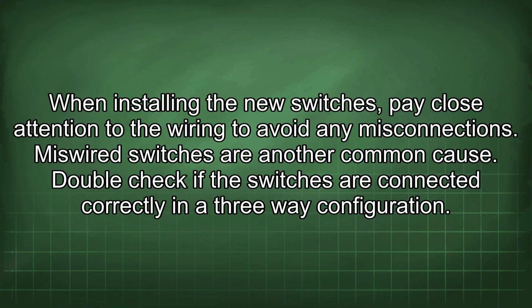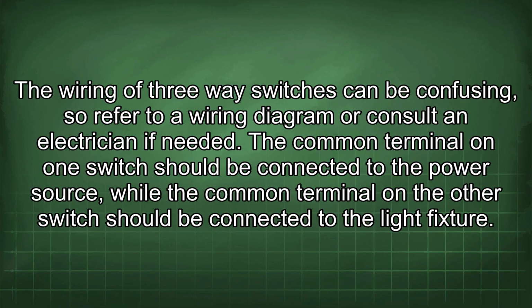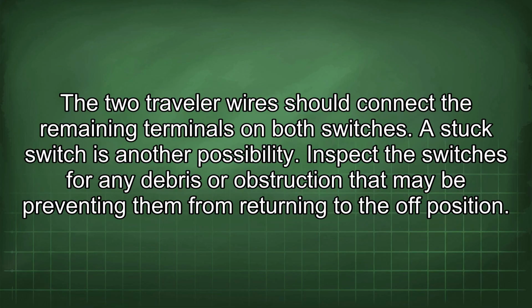Miswired switches are another common cause. Double-check if the switches are connected correctly in a three-way configuration. The wiring of three-way switches can be confusing, so refer to a wiring diagram or consult an electrician if needed. The common terminal on one switch should be connected to the power source, while the common terminal on the other switch should be connected to the light fixture. The two traveler wires should connect the remaining terminals on both switches.